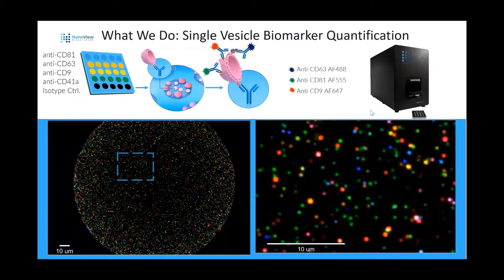When we zoom in, we probe this for content at the individual vesicle level. We can also size these vesicles. We show three-color staining, giving up to seven different phenotypes. You can size these independently in the label-free mode, so you have a size distribution and detection of up to four surface markers multiplexed on the same spot. The spots are in replicate, and these measurements will be composed of thousands of individual vesicles when you look at the different phenotypes present.